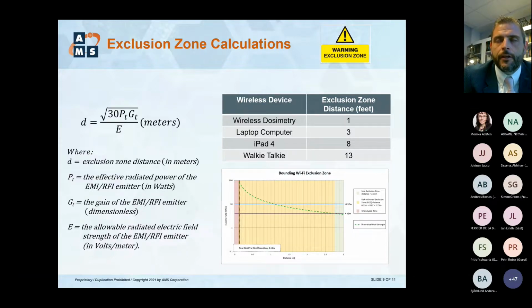One is going from what I'm going to call the safe exclusion zone approach to a risk-informed approach. With that, the exclusion zone assumes a certain field strength. Traditionally, it's been 4 volts per meter. Keep everything below 4 volts per meter because in the US, we tested 10 volts per meter. So that gives a level of margin. It's been tested at 10 volts per meter, and I'm going to keep everything below 4 just to have some margin. That's what we call the safe exclusion zone.